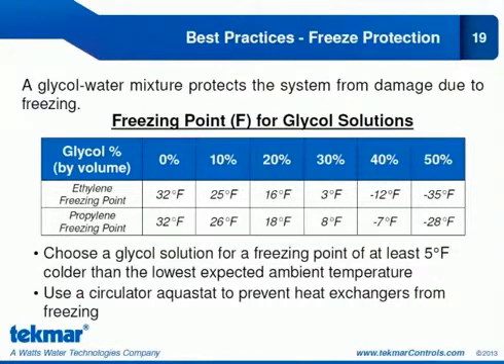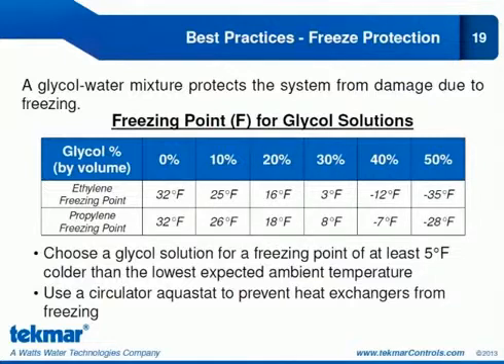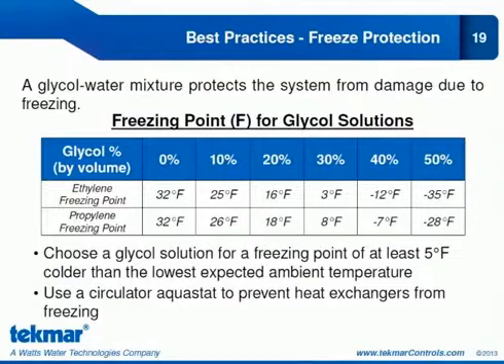Another best practice is freeze protection. Snow melt systems typically operate at very low temperatures, so a glycol-water mixture is essential to ensure the system does not experience damage from freezing. There are two glycol-water mixtures: ethylene and propylene. Propylene is the standard because it is non-toxic, unlike ethylene which is toxic. We recommend propylene, and you want to choose a solution that gives you a freezing point at least 5 degrees colder than the lowest expected ambient temperature — typically about 40% propylene. We also recommend using a circulator aquastat to prevent heat exchangers from freezing.